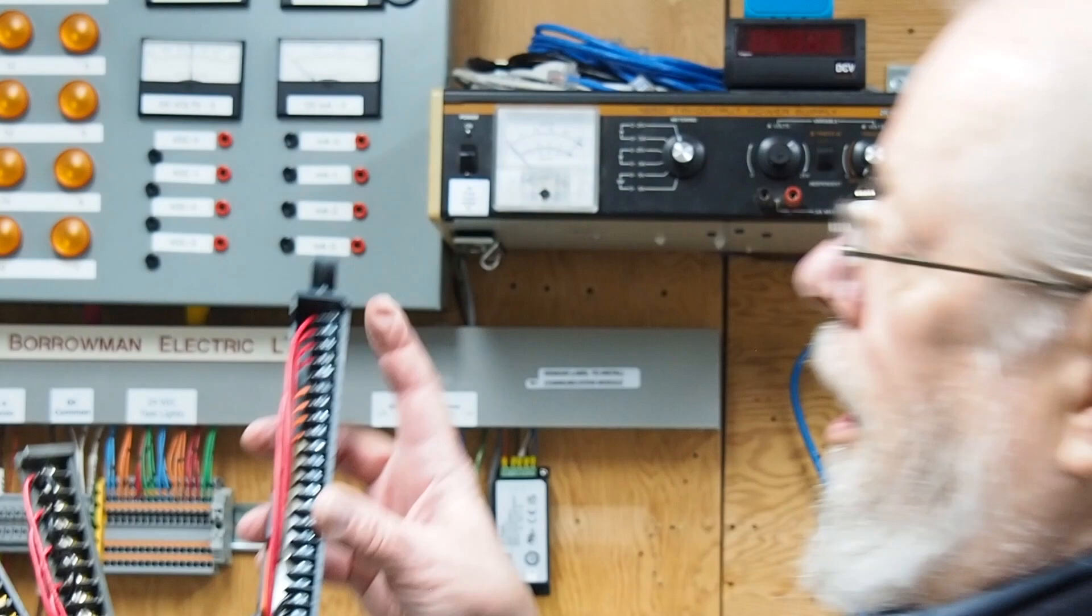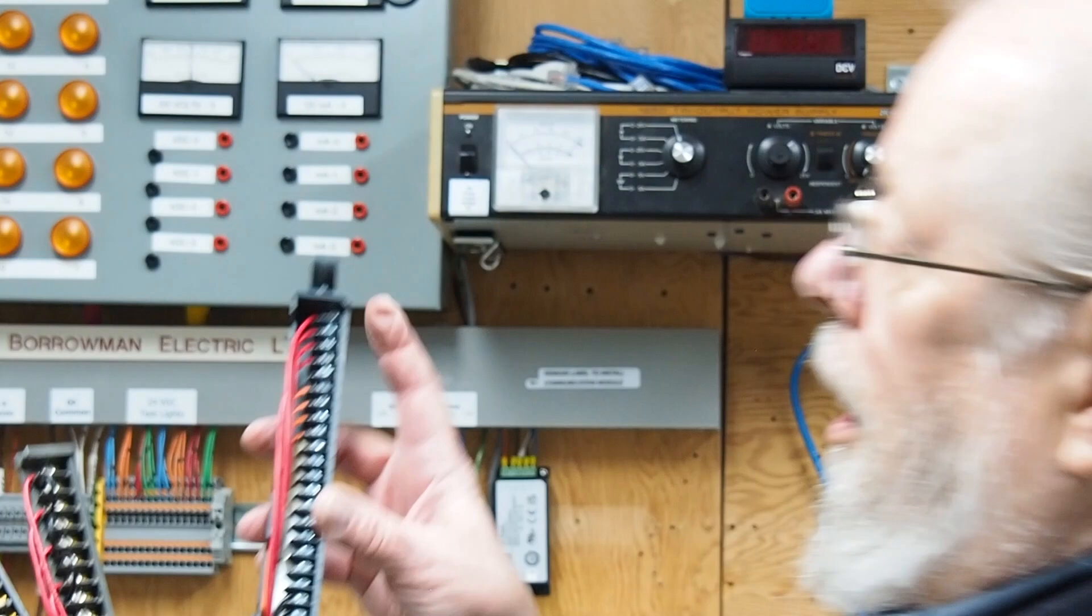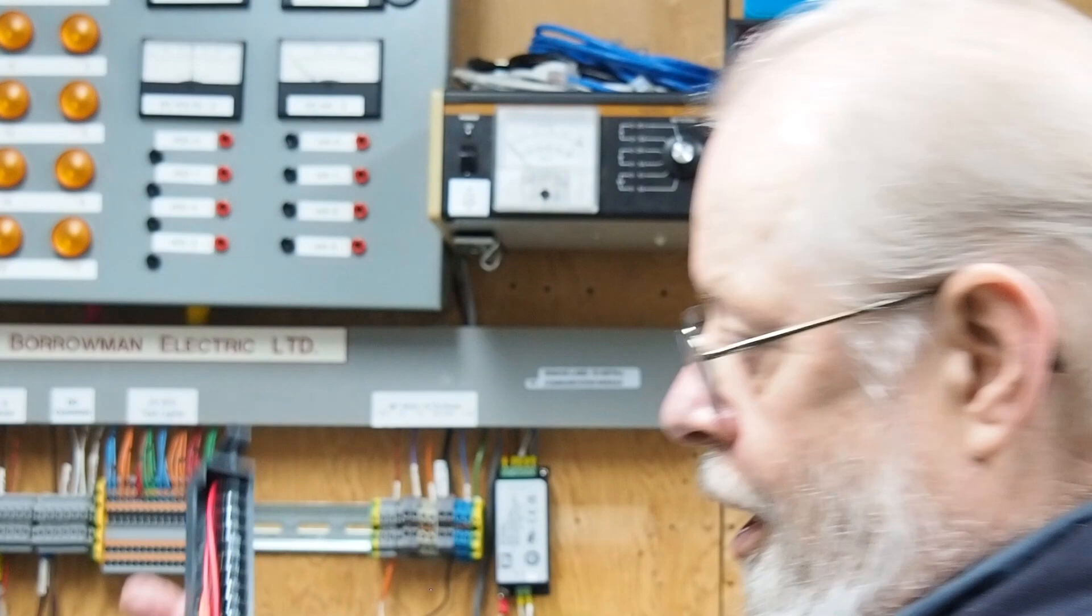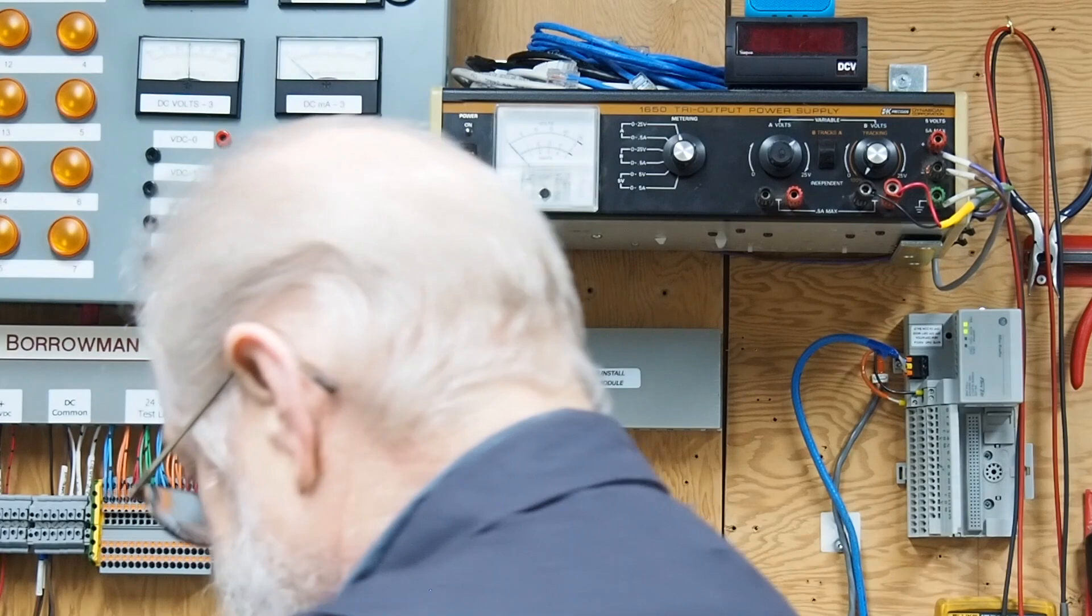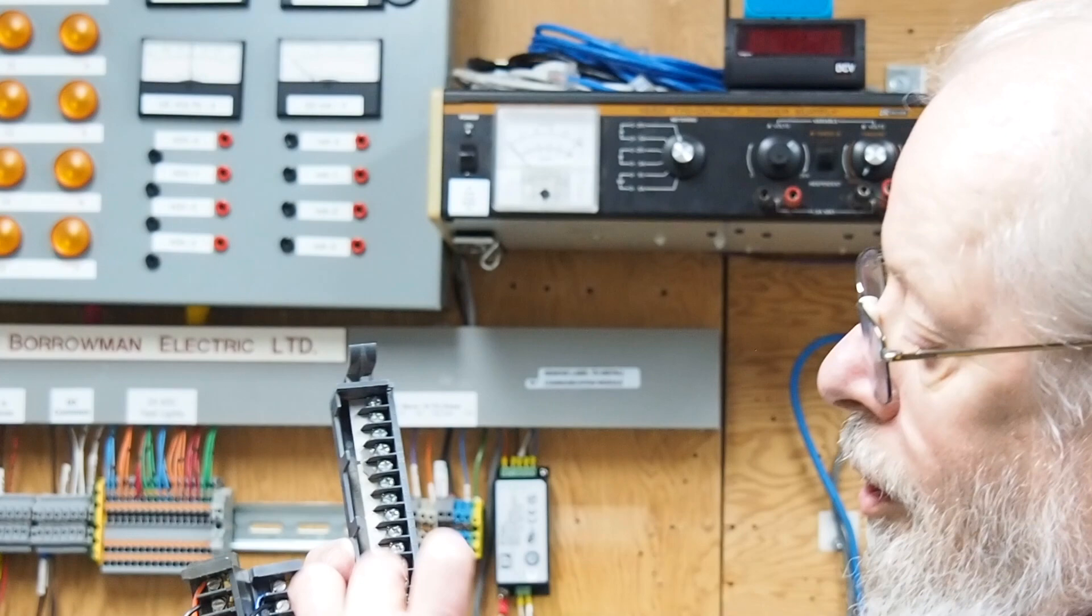I have set up two sets of four channels each. So I used two of them at one time, and that gives me eight inputs. On the first round, I'll grab the first one here, input one through eight off of the two cards, and on your unused channels, you have to jumper them together on the wiring arm to common or negative. And then for the second round, same thing again, except that now I'm doing the last eight channels and the first eight are jumpered.